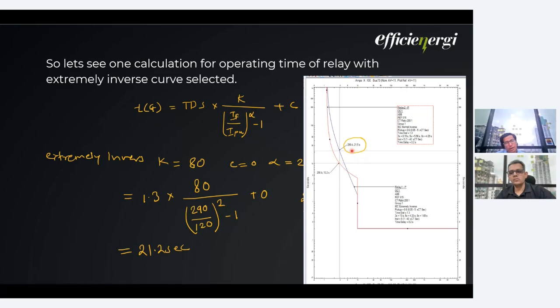Here you can see the time is delayed for the same magnitude. So this is extremely inverse; the inversity in this region is very extreme. Here also you can see the difference. As you move on to higher and higher magnitudes, the time will change. This is a break point. Here the extremely inverse curve takes over and trips faster than the standard. In this region, the standard curve trips faster than the extremely inverse. Both characteristics are used when protecting particular equipment. For a transformer we will use this one, and for feeder protection we will use standard inverse, because for a feeder we want a delayed time for a higher magnitude.